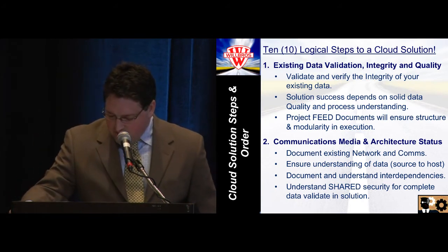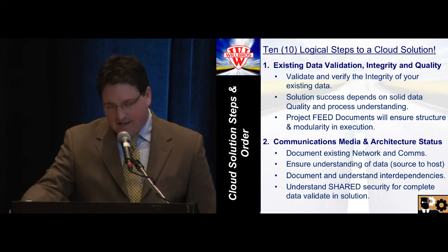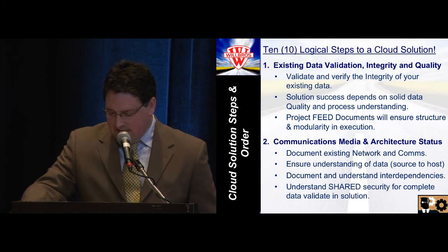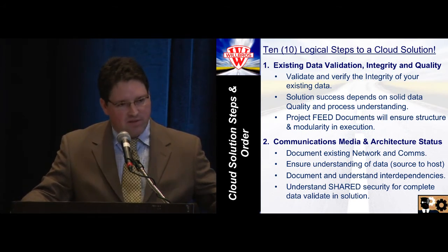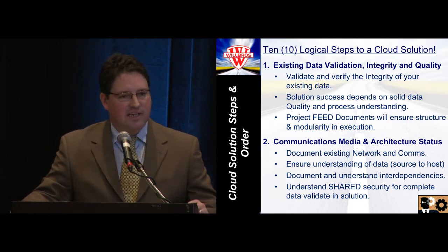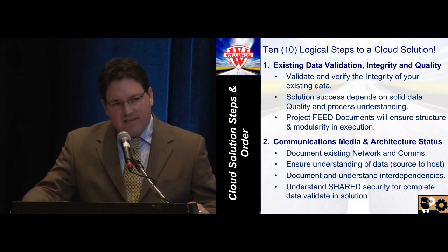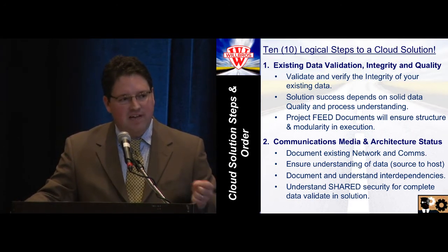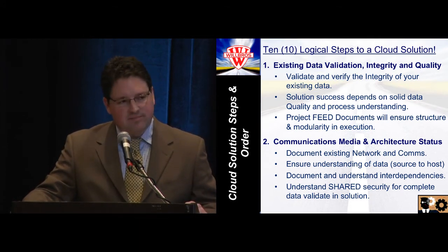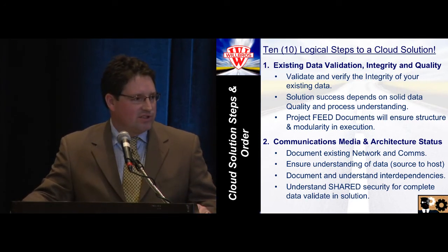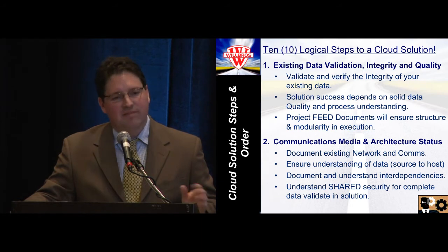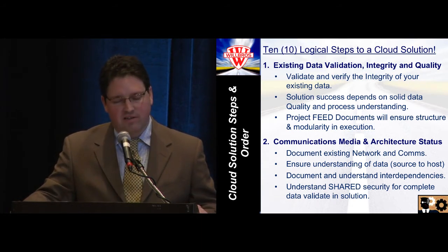Step two was to look at communications media and architecture status. We verified and documented all communications and network architectures, allowing us to understand the data all the way from the instrument through the chain to the SCADA system, leak detection system, and historian. We had to understand all interdependencies — in a retrofit, data can be shifted around and you have to validate it. At this point, we could understand the shared security required. A cloud solution, regardless of application, is basically a database — garbage in, garbage out — so spend the time up front on data verification and quality.